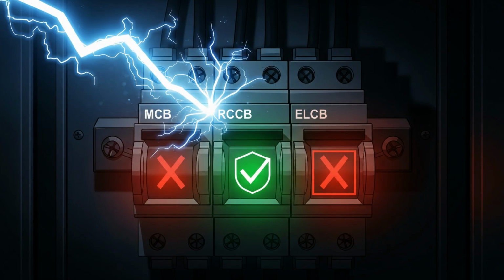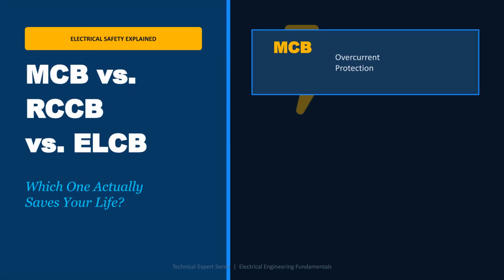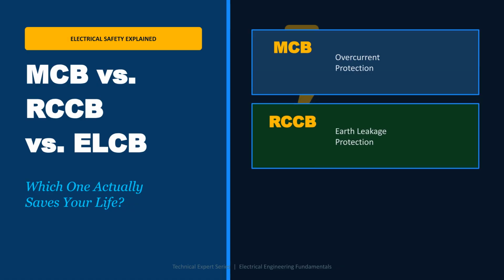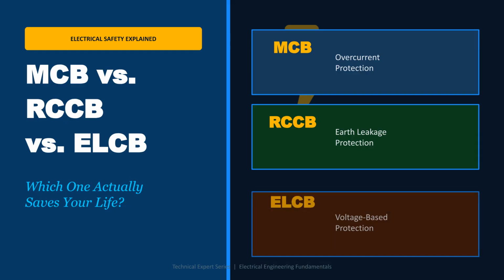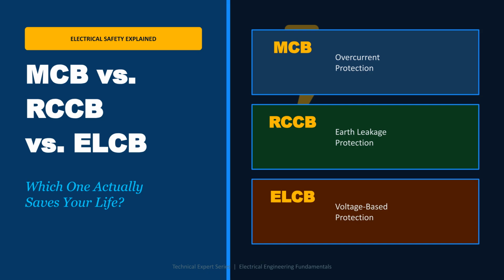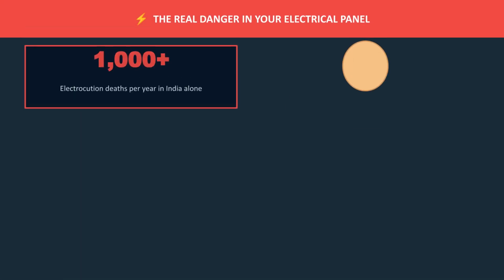Welcome. Today we'll clarify the difference between MCB, RCCB, and ELCB. Which device actually saves your life in an electrical emergency? By the end of this video, you will know exactly what each device does, when it works, and when it fails. We are comparing the miniature circuit breaker, or MCB, which provides overcurrent protection. The residual current circuit breaker, RCCB, designed for earth leakage protection, and the earth leakage circuit breaker, ELCB, which uses voltage-based protection.